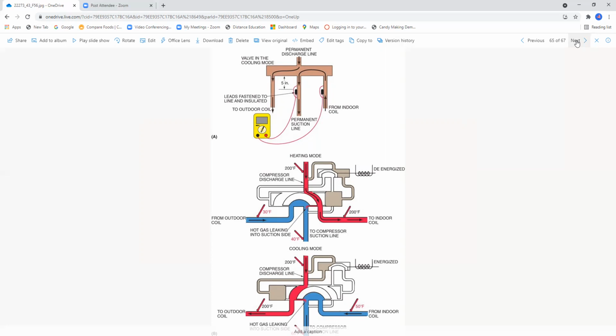So this is going to be found on page 1308 of your textbook under figure 43.56. The method for checking performance of a four-way valve using the temperature comparison. So basically, you're looking at the temperature comparison right here. Okay, if we have more than 3 degrees, much as I hate to tell you this, we got a leaking valve. We don't like that. So basically, in this situation here, let's take a look at this first illustration. From the outdoor coil, we got 30 degrees going in here, 40 degrees coming out here. And why is that? Because we're leaking internally right here.